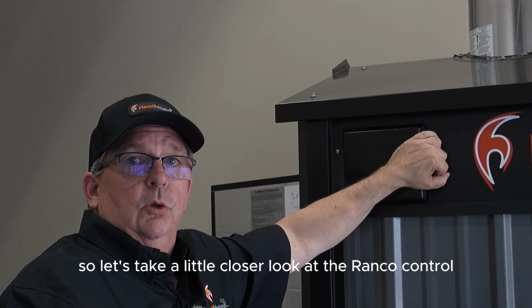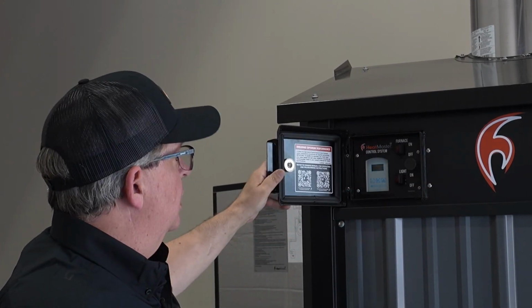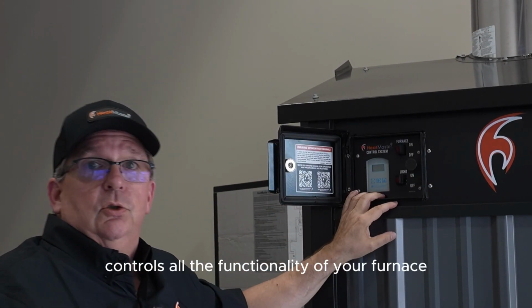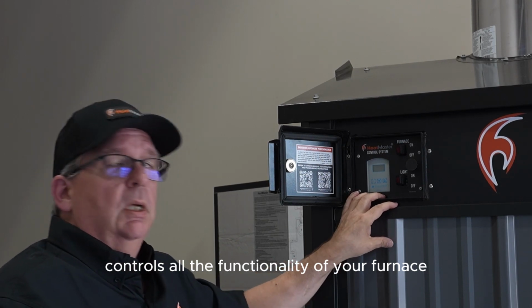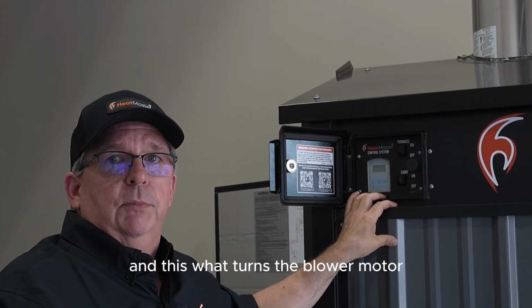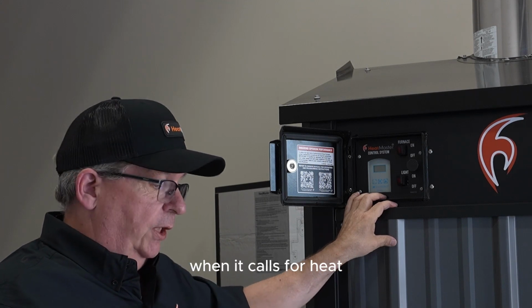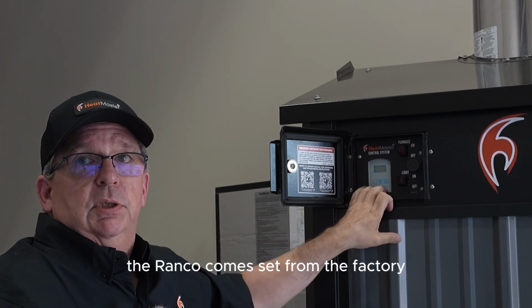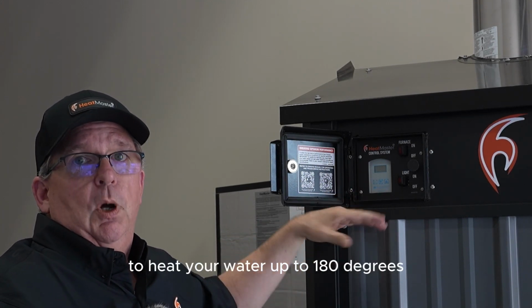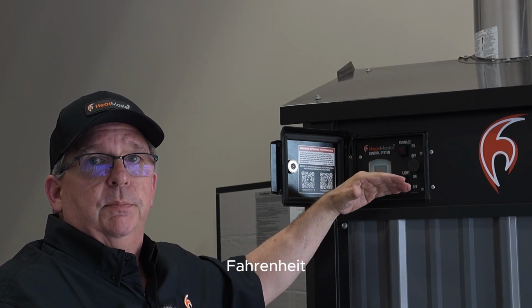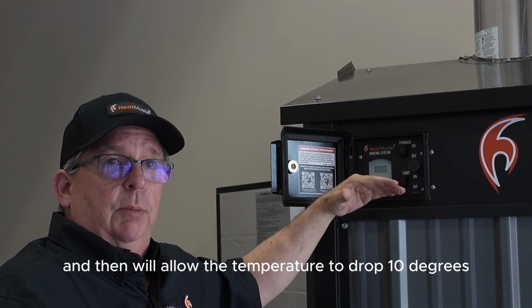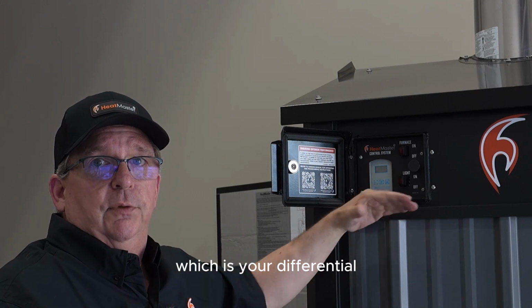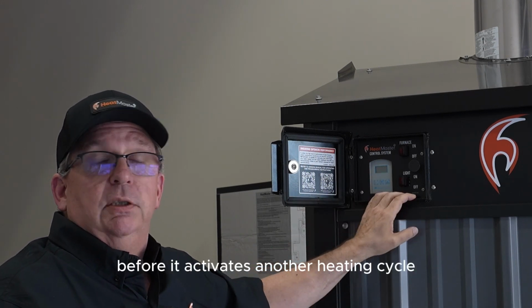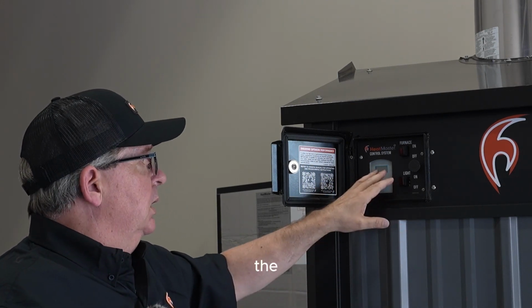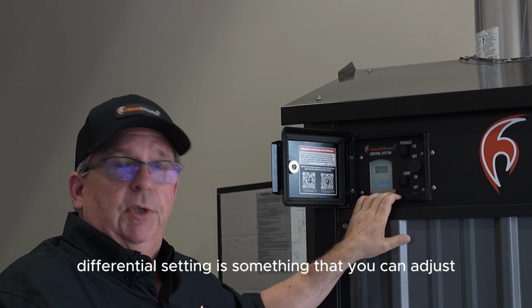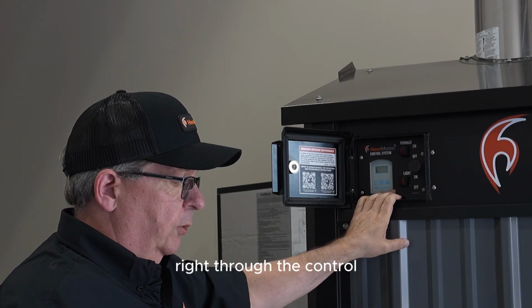So let's take a little closer look at the Ranco control. The Ranco basically controls all the functionality of your furnace, and it's what turns the blower motor and the actuators on and off when it calls for heat. The Ranco comes set from the factory to heat your water up to 180 degrees Fahrenheit. It then will allow the temperature to drop 10 degrees, which is your differential, before it activates another heating cycle. The differential setting is something that you can adjust right through the control.